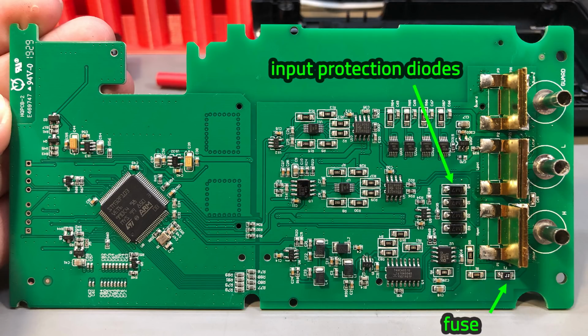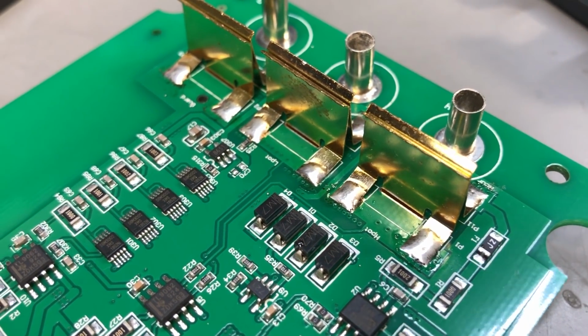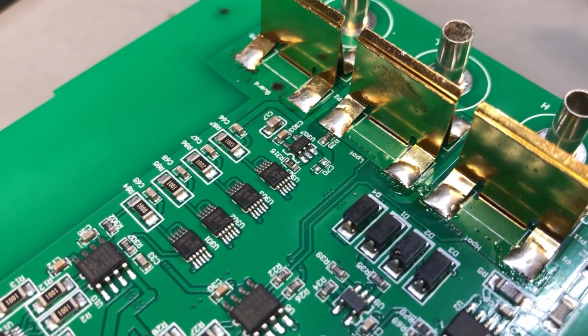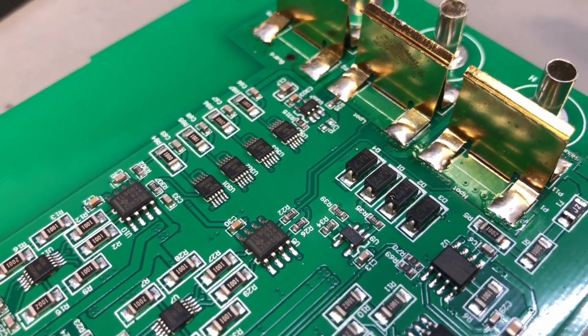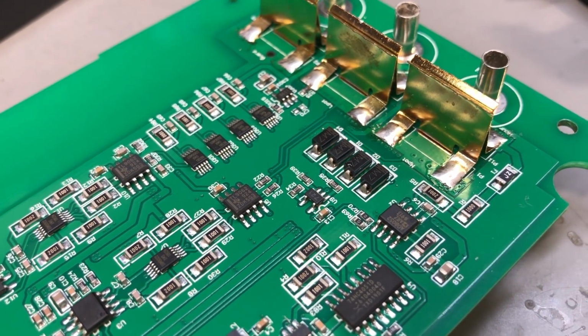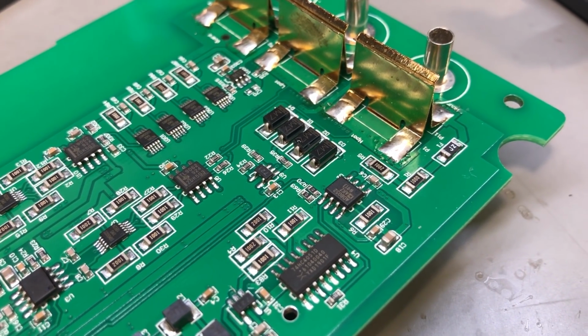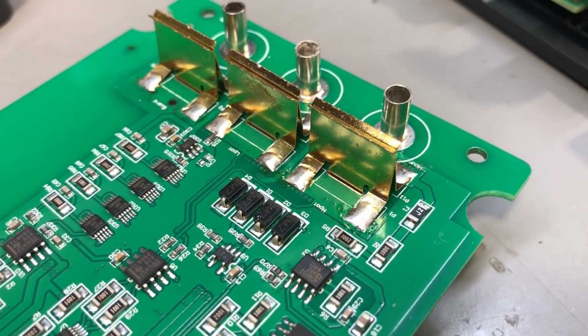On the input section, we have a bunch of diodes, some input resistors in 1206 package, and a resettable fuse. I see no other protection devices, no MOVs for example, and I'm not sure how needed those are. This is, after all, designed to measure passive components, resistors, capacitors, inductors. Generally, the soldering is very good and clean, no flux residue, with the exception of the input blade terminals, which might have been hand soldered last, and there is a bit of flux residue on those.